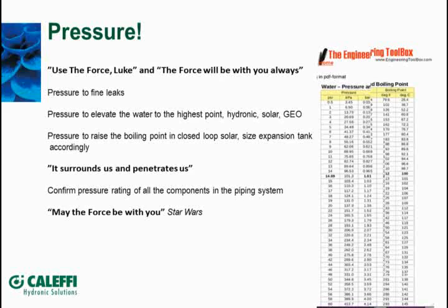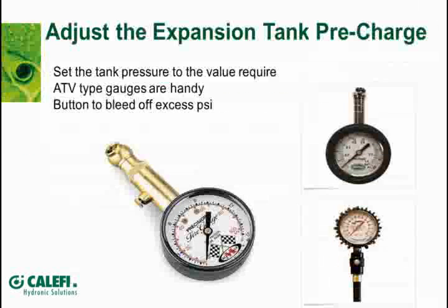So now, the other thing you're going to have to keep in mind is when you pressurize your system and you fill your system, the expansion tank that's on there needs to be adjusted to the fill pressure also. You're going to want to do that before you pump the fluid in, or before you turn the fill valve on and fill it. Do it before there's any pressure in it. Just take a little accurate pressure gauge and check the expansion tank pre-charge. Now, most of them on the side of the tank are going to say 12 pounds fill pressure, but they're not always what they say.